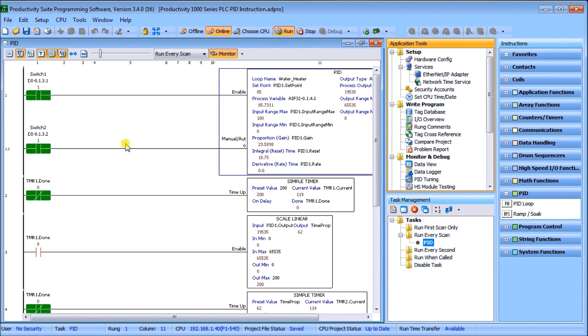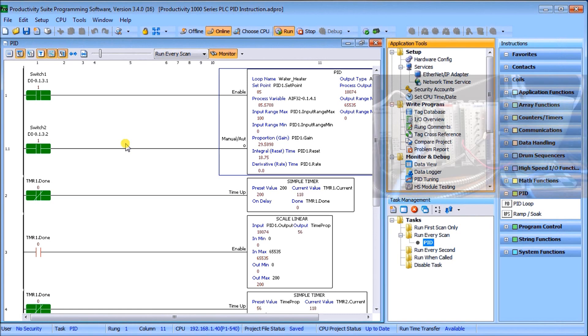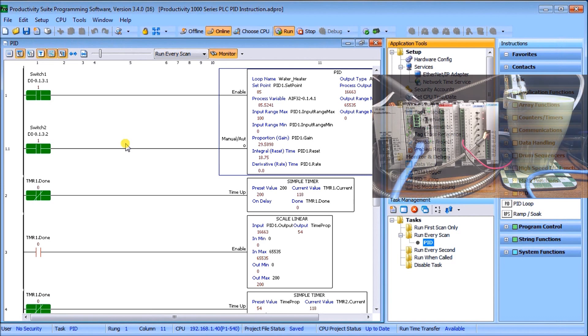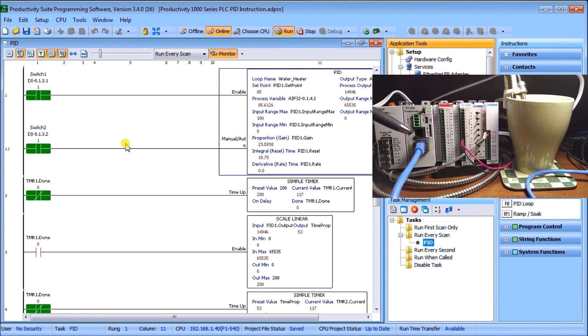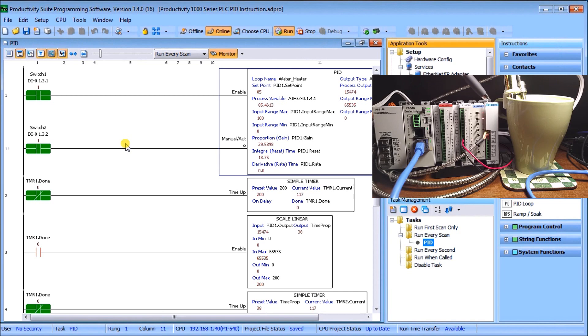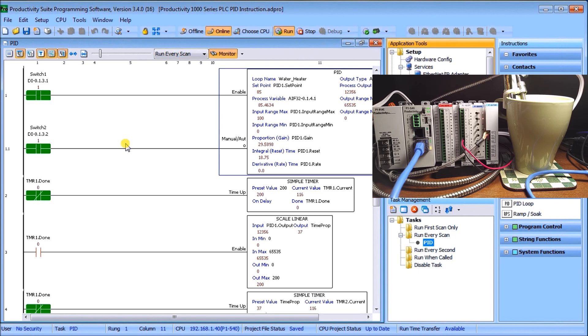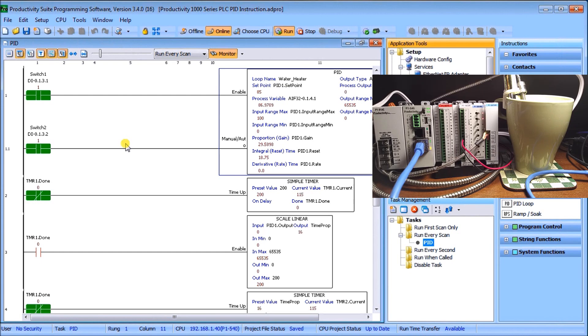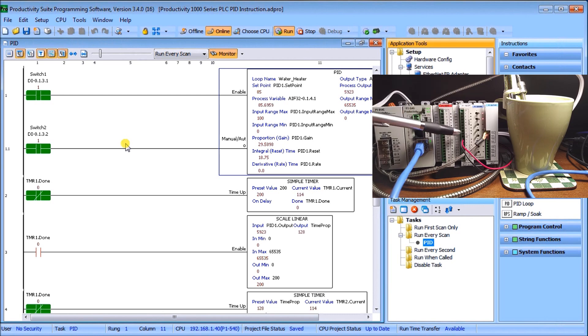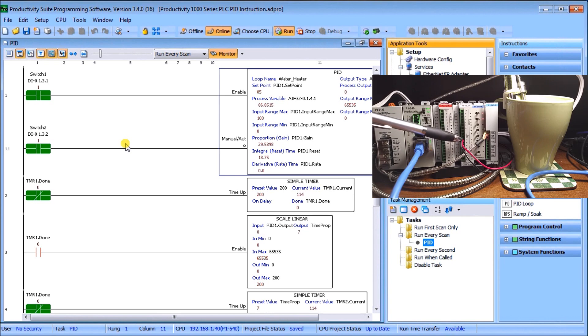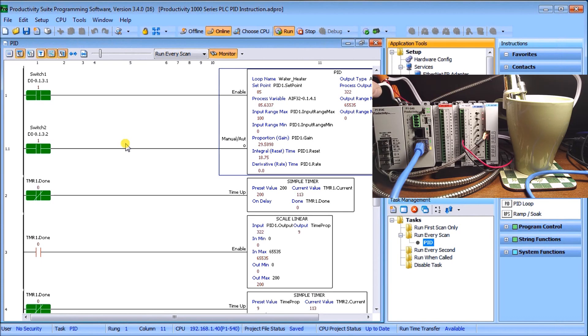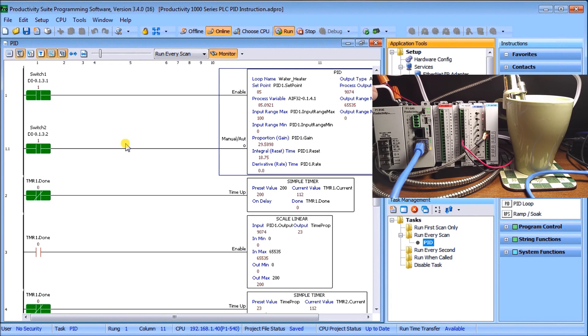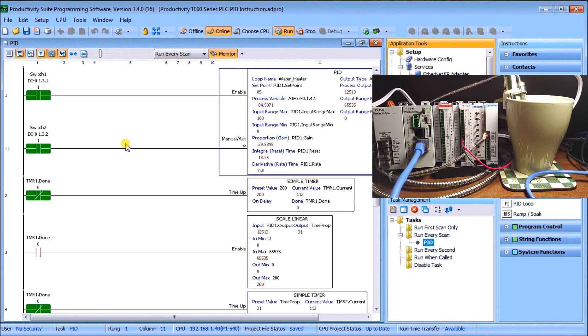Let's first look at the actual hardware that we have here. So here's my Productivity 1000 and you see I'm connected through my Ethernet port here. Then we have our thermocouple, which is connected with my thermocouple input, which is located right down in here. You can see that's in a cup of water right now. Then we have our immersion heater, which is actually connected to 120-volt supply, and we're using the first relay here to trigger or to turn on and off that heater. That heater actually, the output has been spliced into one of the ends of the cord connecting into the wall socket in order to provide that on-off action that I'm looking for.